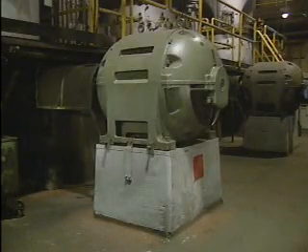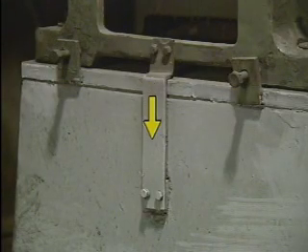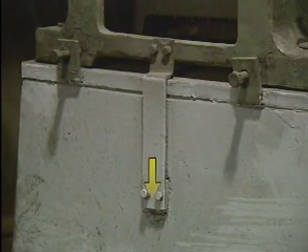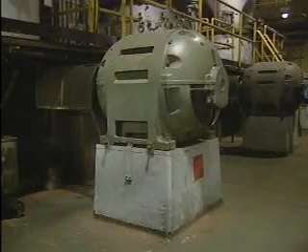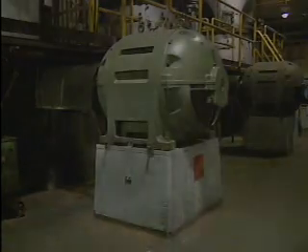If the motor develops a fault, the normally de-energized housing could become energized. But through proper grounding, any current that's flowing in the housing because of a fault condition is directed to ground through the grounding strap and back to the motor's source of voltage instead of through a worker.